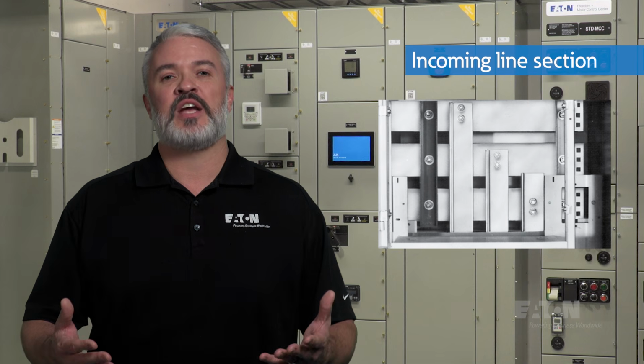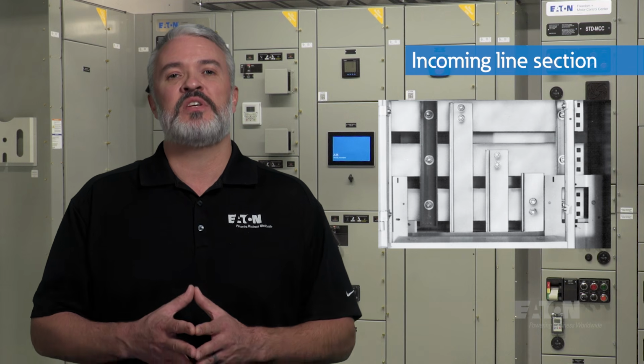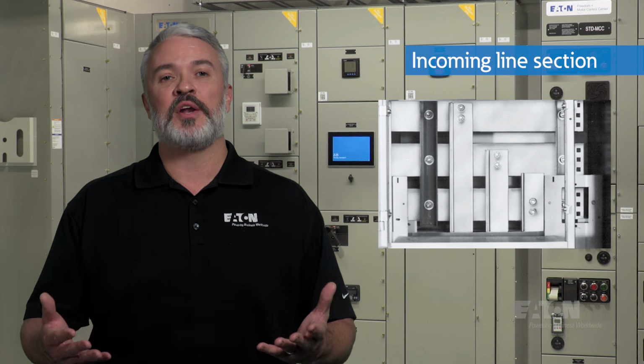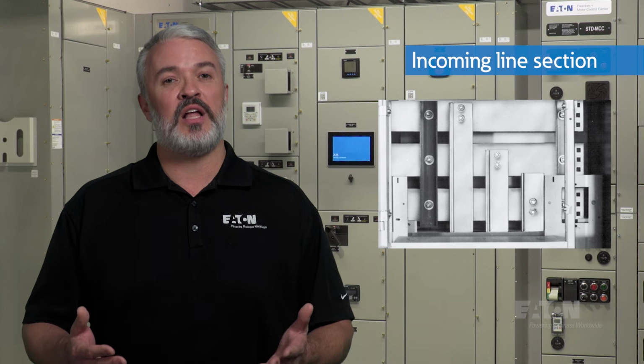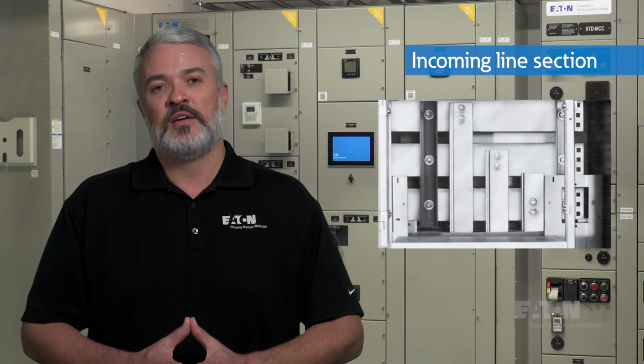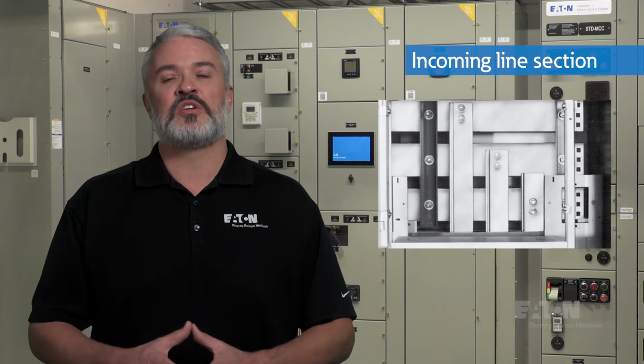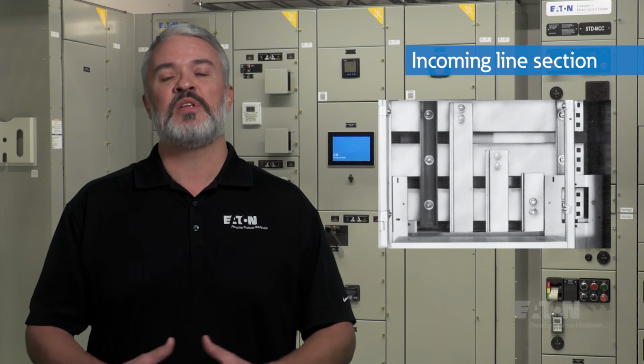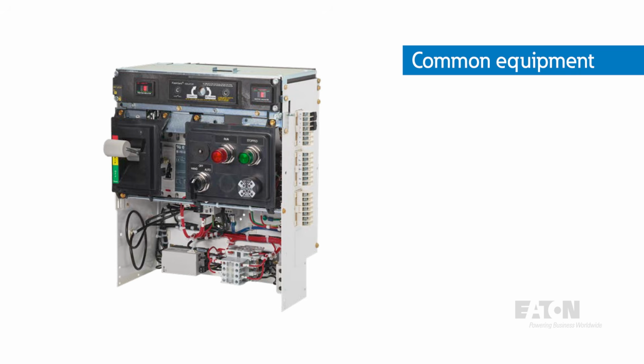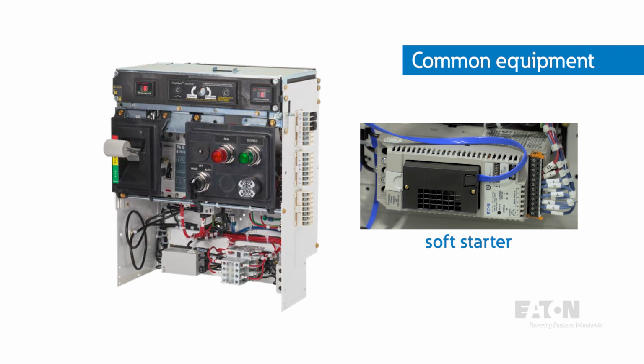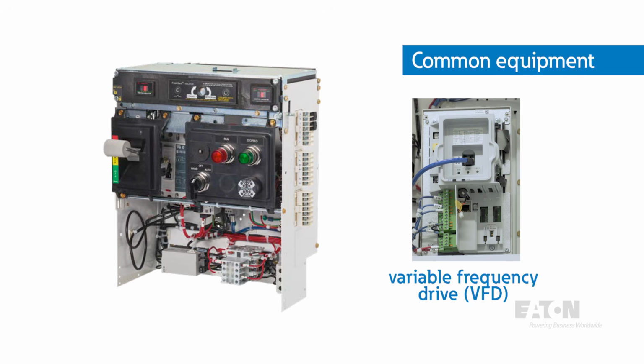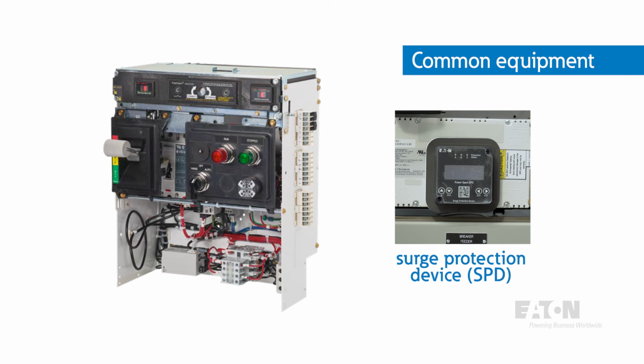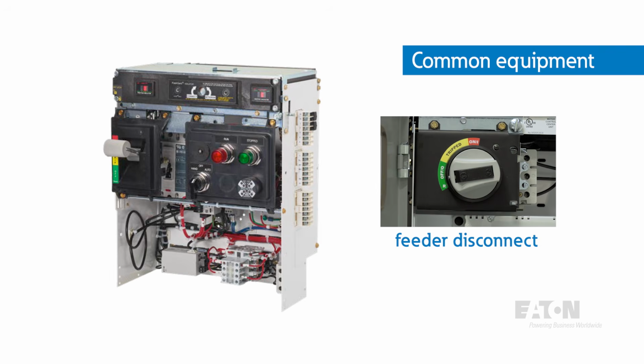The incoming line section is where the line cables enter the MCC from either the top or bottom and are easily terminated onto main lugs or connected to a main disconnect. All incoming line sections comply with NEC wiring bending requirements as adopted by UL. The common equipment installed inside a bucket include motor starters, soft starters, variable frequency drives or VFDs, a surge protection device or SPD, a power meter, and feeder disconnects.